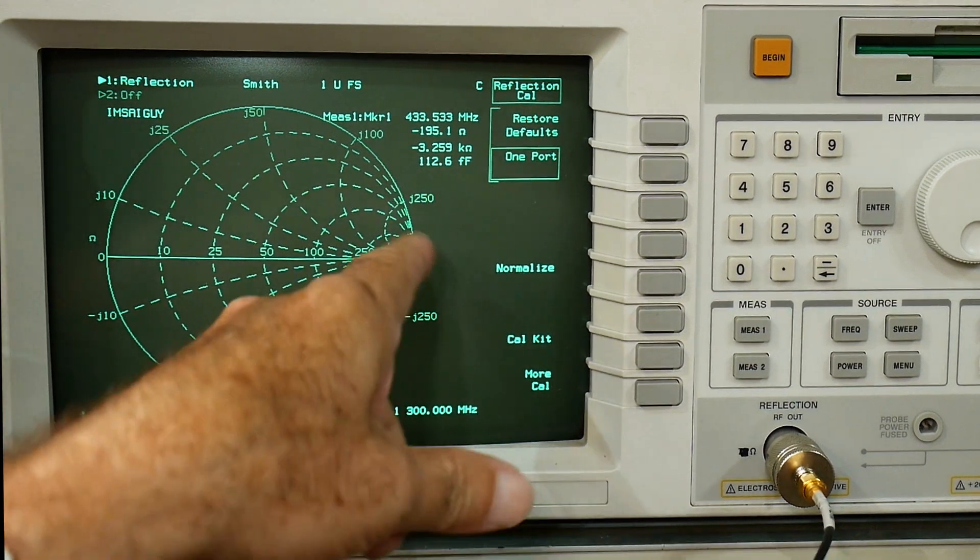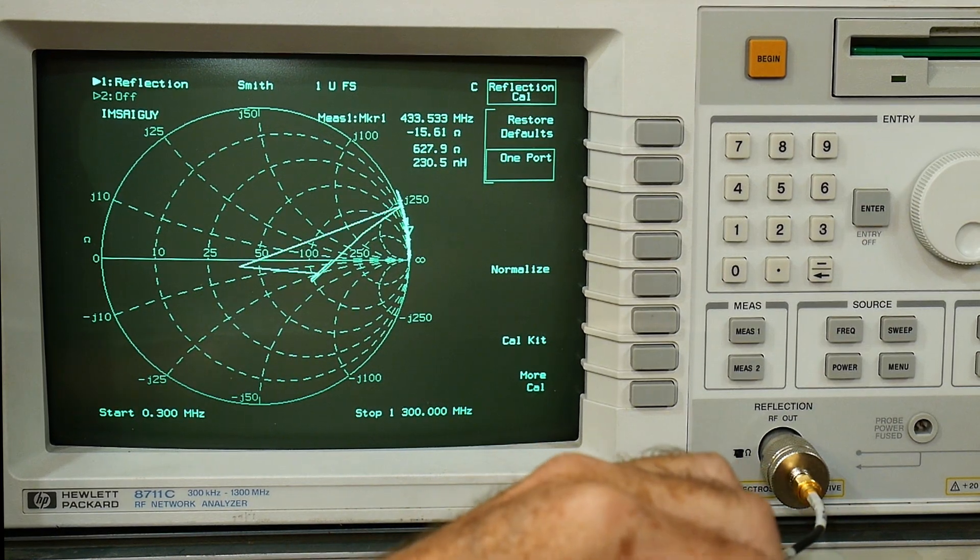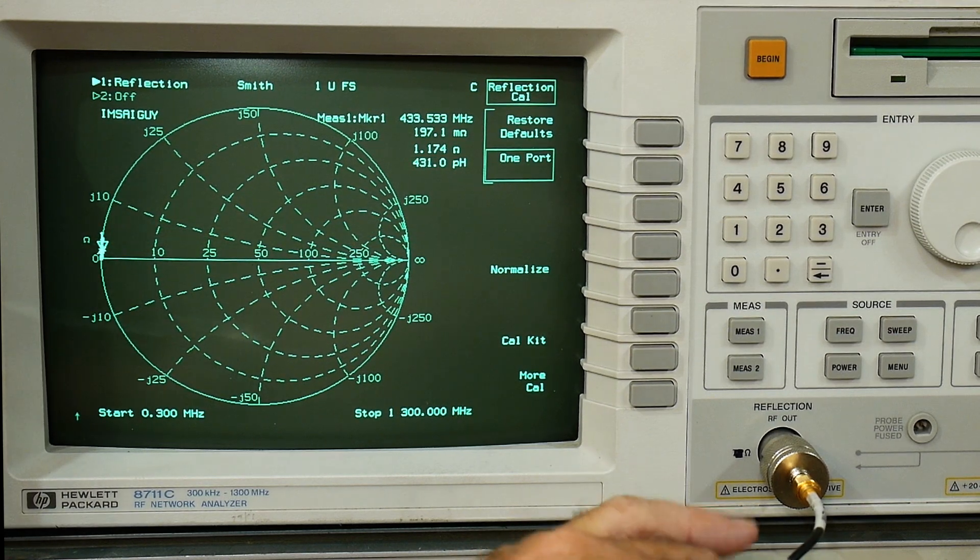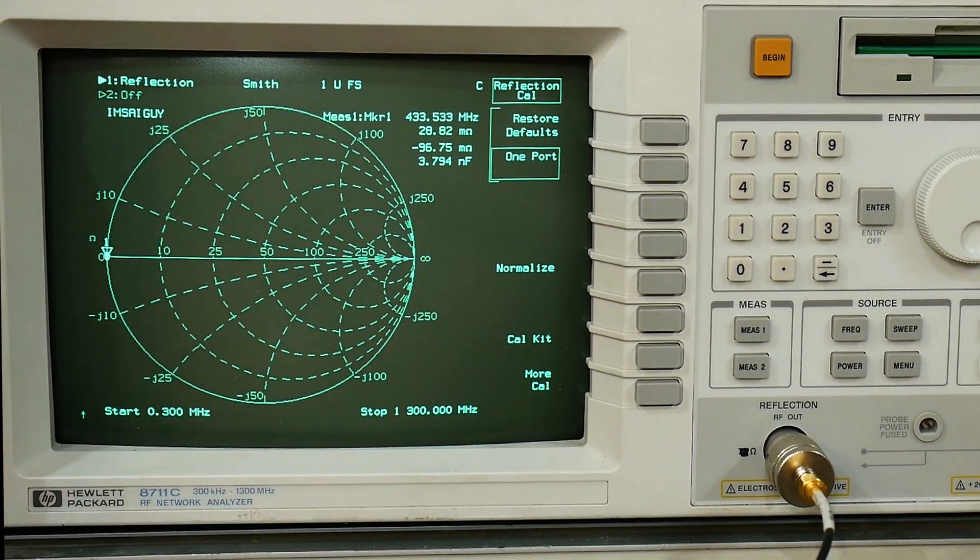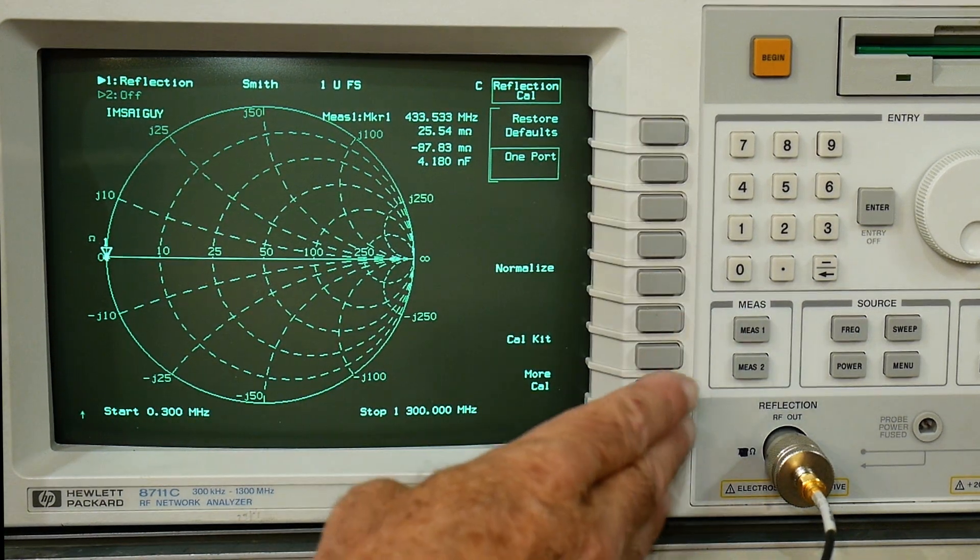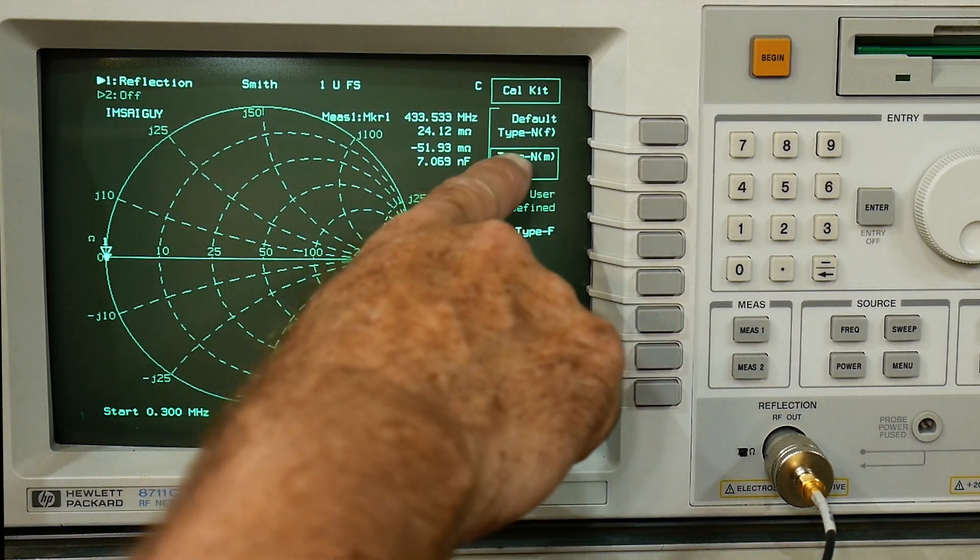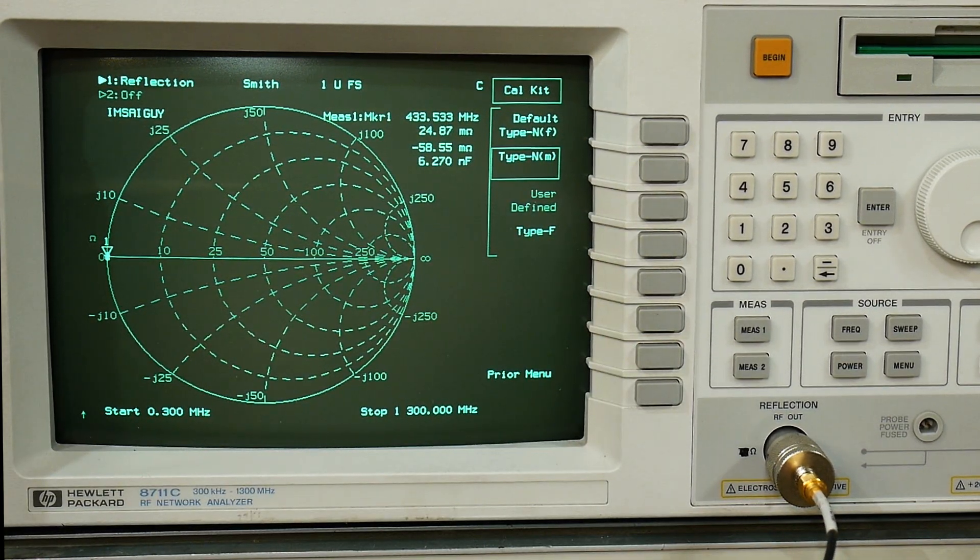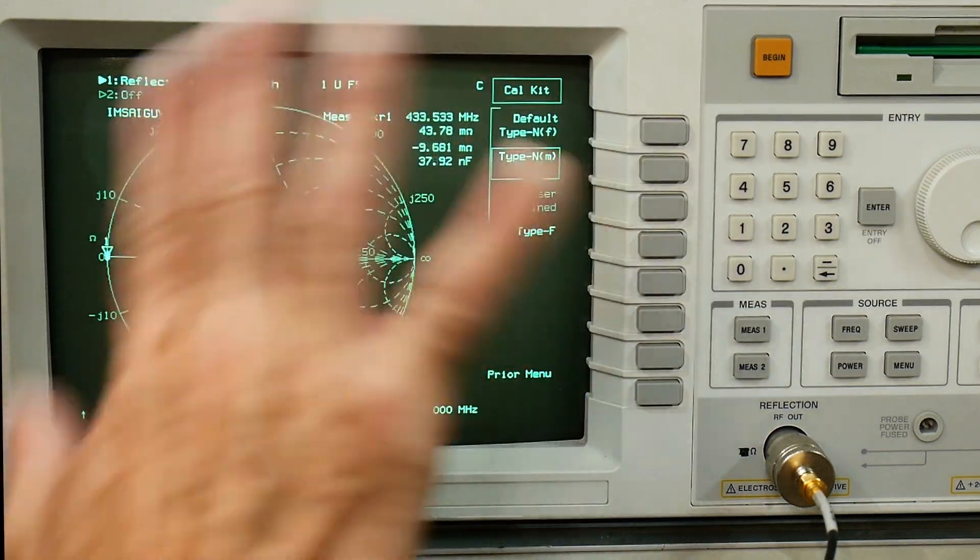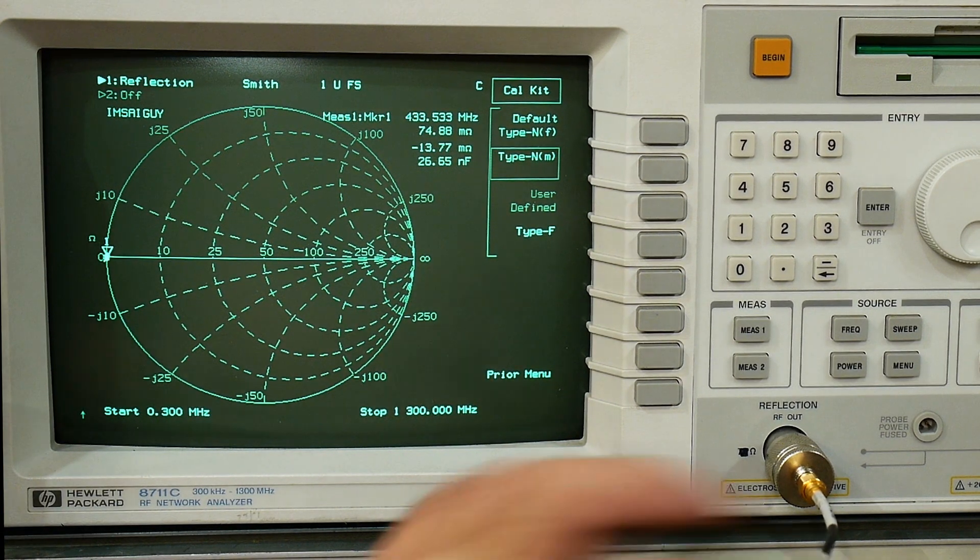So let's go back and look at that open again and you can see that now it's measuring very well. And if we measure the short, had we used the other one it would have given us an error. We'll go to the short and you can see that we're measuring very well so now we're perfectly calibrated. So that's the trick if you get one of these things, make sure that you go into the cal kit and choose type N. I haven't tried type F yet but do type N and everything's fine. Do not use default.